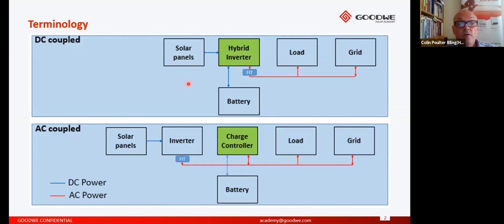So if you were thinking that you could now replace that system with an all-in-one hybrid inverter, you have to be very careful, because that feed-in tariff meter is going to be connected on the AC output side of the on-grid connection. If they were to charge that battery from the grid and release that energy back out of the battery, that is going to pass back through the feed-in tariff meter.